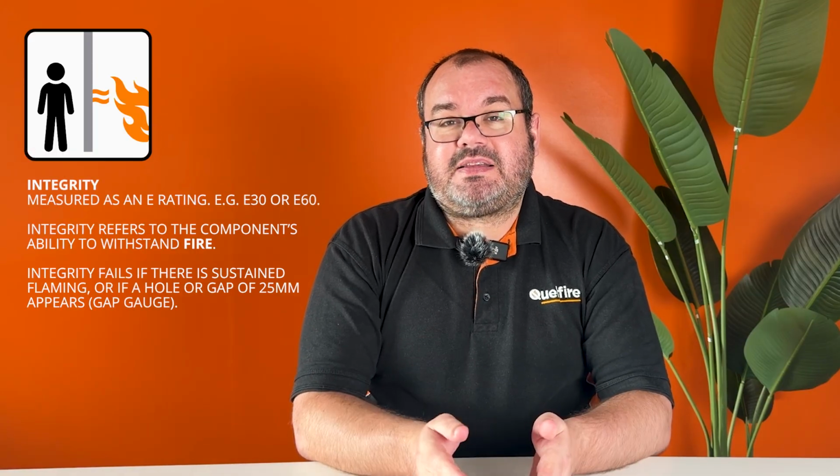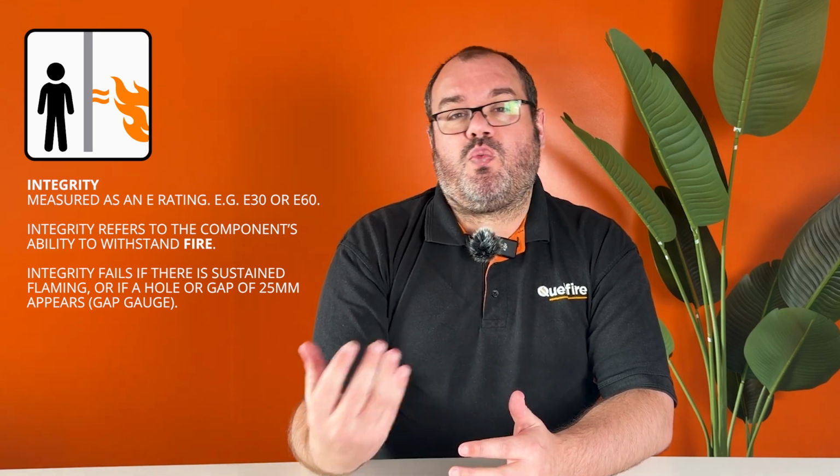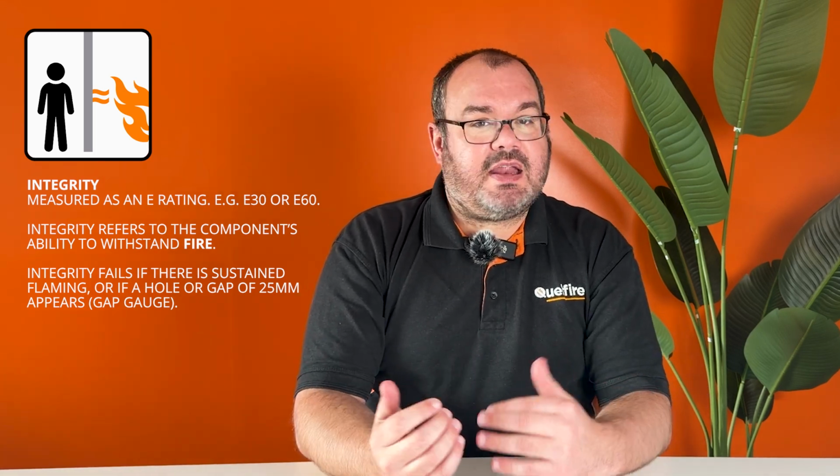So if we look at integrity first, the basic term of this is the ability to resist the fire from getting from one side of the supporting construction, say one side of a wall, breaking through any small gaps to the other side, the non-fire side, or vice versa from the underside of a floor, because we always test floors or ceilings from the underside, breaching through that supporting construction to the non-fire side, space above the floor construction. So that is obviously the important thing. You're trying to stop that fire from breaking through and spreading into another compartmentation area, hence why we discuss compartmentation.